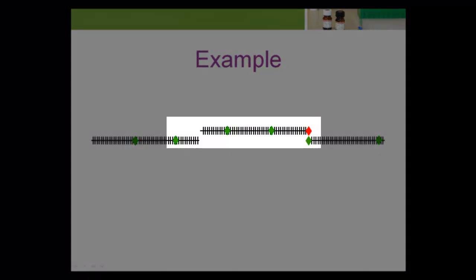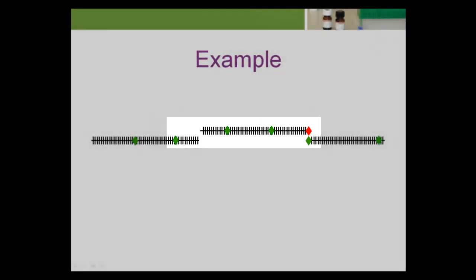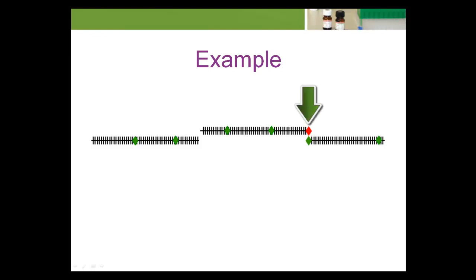Let's look at an illustration of this point. The horizontal axis represents time. Each vertical line represents a patient specimen being tested on the instrument. Each diamond represents a QC event where QC specimens are tested and QC rules are applied. A green diamond implies the QC results are accepted. A red diamond means the QC results are rejected. At a point between the second and third QC event, an out-of-control error condition occurs, causing a sustained shift in the testing process. Given the magnitude of this particular out-of-control condition and the power of the QC rules, the error condition isn't detected until the third QC event after it occurred. Each red asterisk denotes an unreliable patient result that was produced during the existence of the out-of-control error condition.